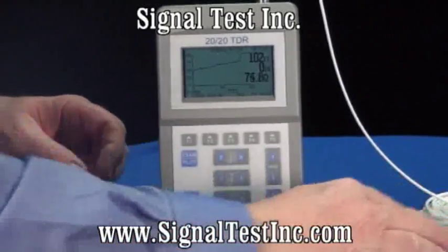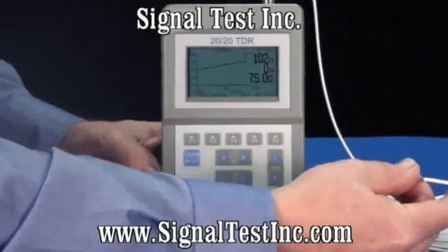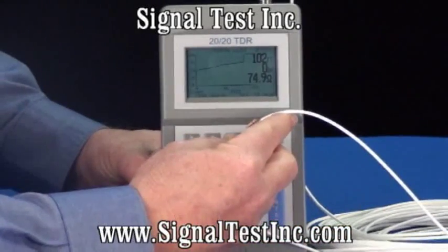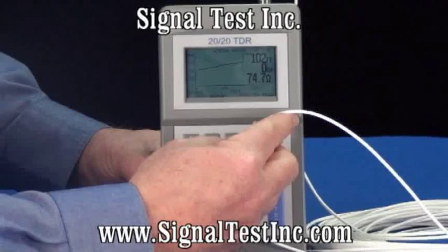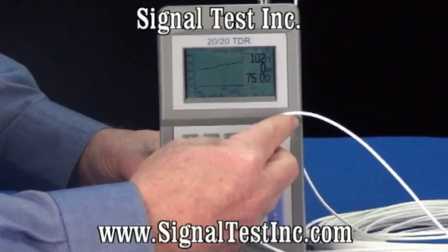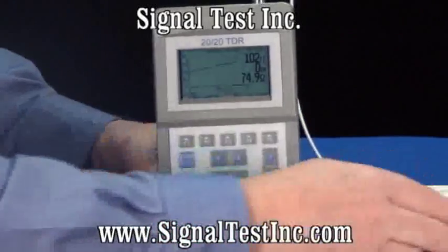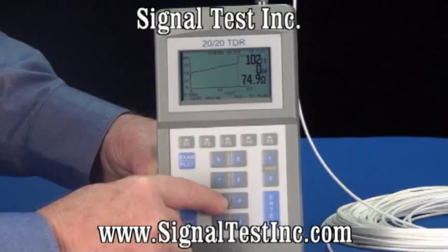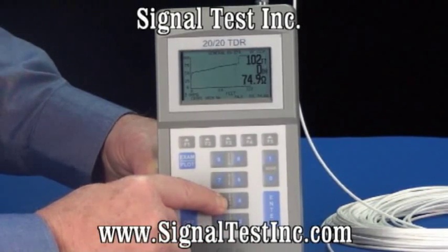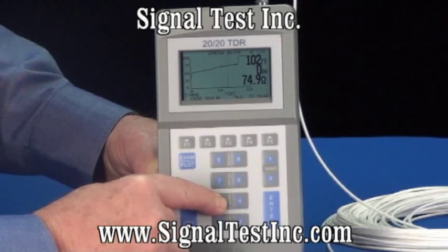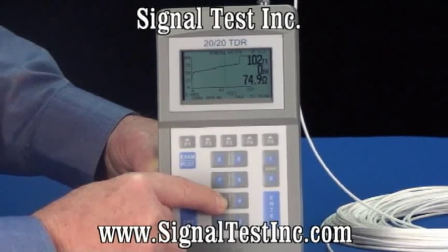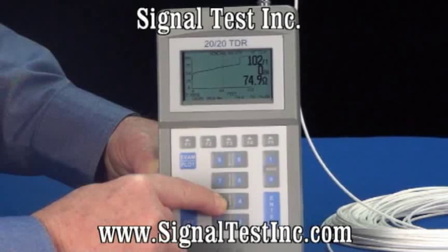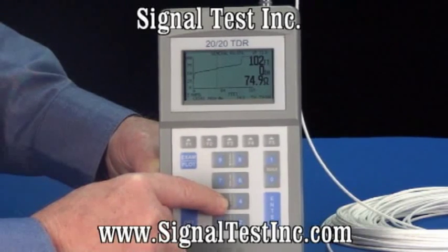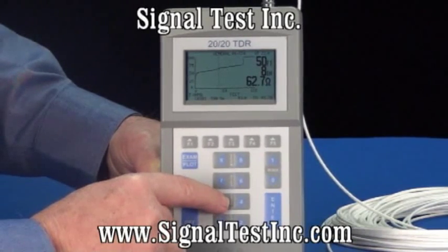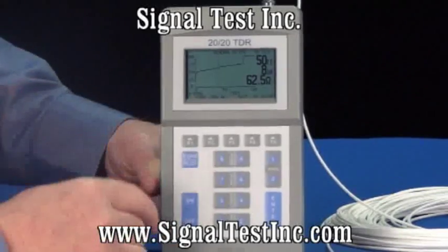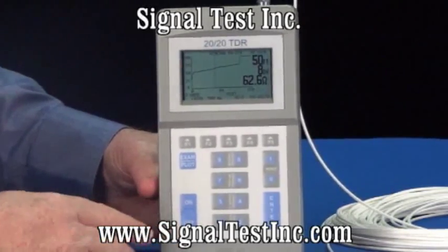Additionally, the piece of RG174 that we're using today has a defect that we built into it. 1/8 of an inch of the shield is missing, and a 1 ohm resistor has been inserted. And I'll take the cursor back to the left and show that defect to you. It appears quite clearly on here. At 50 feet and 8 inches, there is a deviation right there indicating the 1 ohm gain from the resistor.